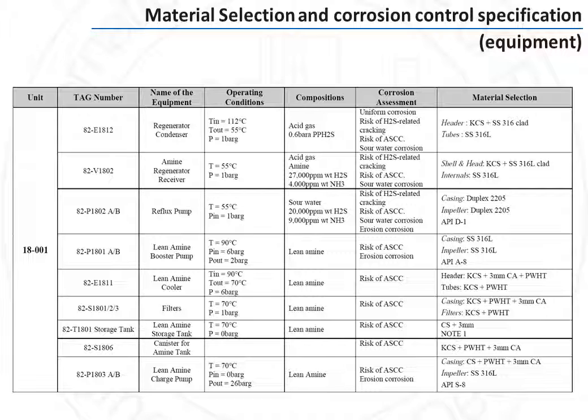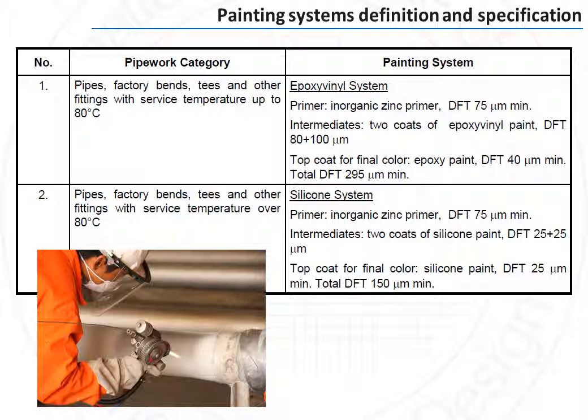The selection of materials of construction does not end the work of the materials specialist. He also specifies the type of coating which must be applied to protect against external corrosion, by defining various systems for various types of conditions — in particular the temperature of the lines and equipment — and issues a painting specification specifying the surface preparation as well as the paint system for every service.